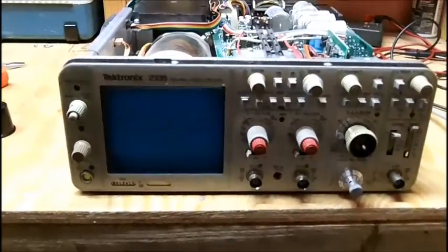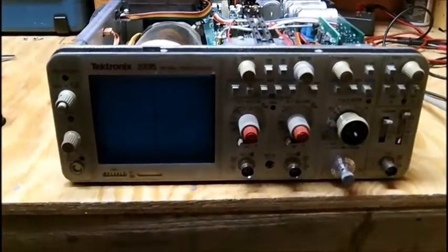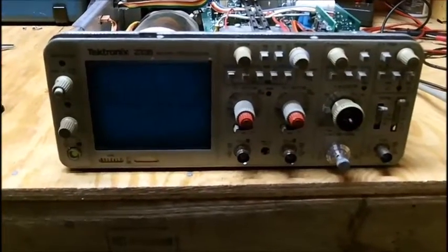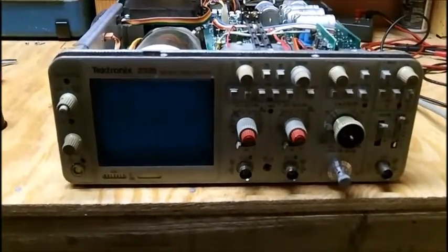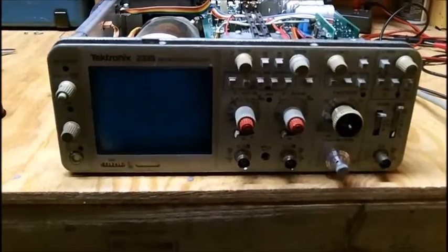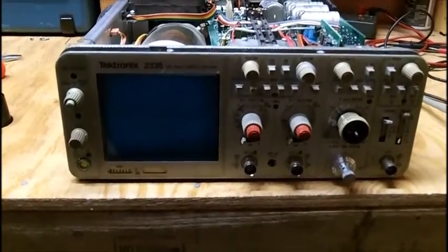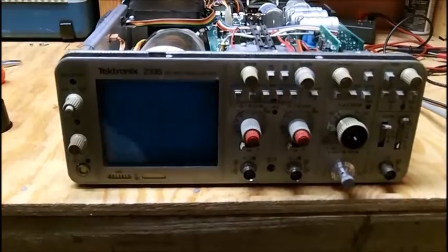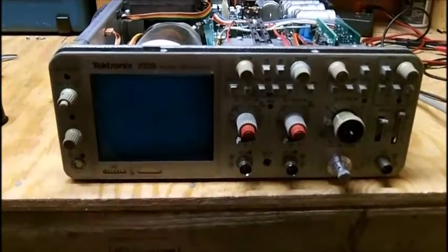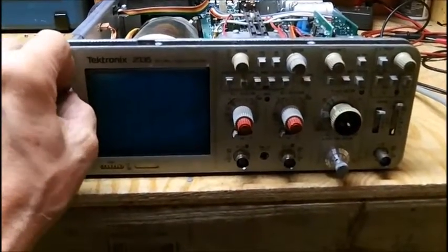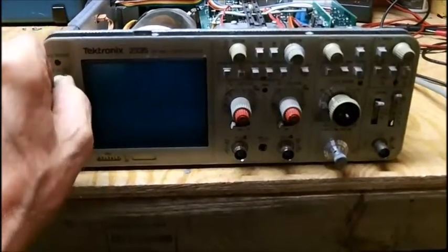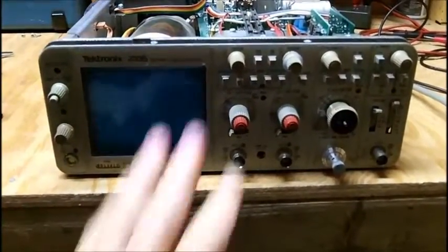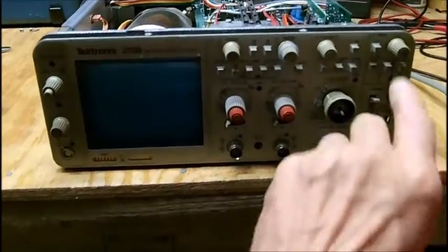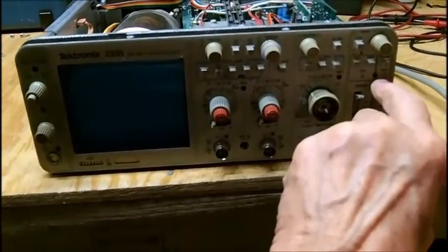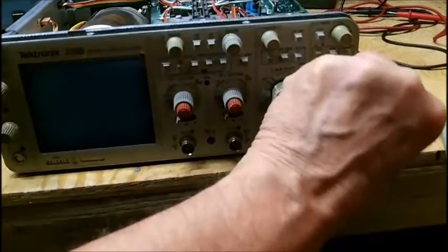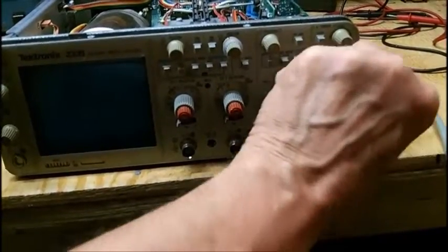Alright, well, I can't do anything with it. I don't have a high voltage probe. I think it's a loss of high voltage. It could even be the CRT itself. Maybe the filament burnt out, because it had plenty of brightness. You didn't have to turn that intensity up very high at all. It just stopped giving a response. Nothing happens here. The only thing you'll get is a flicker of the triggering.